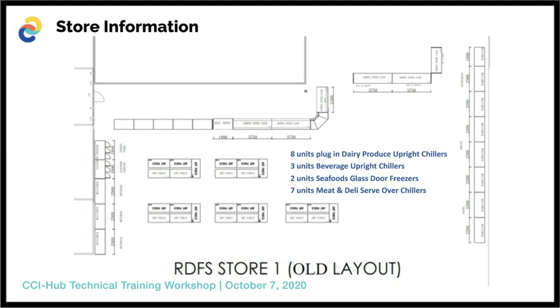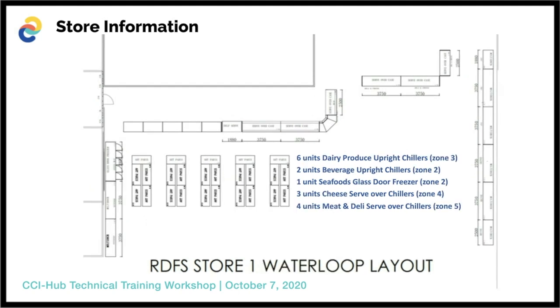After the renovation of the store itself, the way we did the renovation was all wall-mounted refrigerated units are part of the water loop system. The island freezers in the middle are actually plug-in, but are also R290 systems. If you add up the number of units we have here, we actually have 16 units as opposed to the 20 that was the original setup of the store. But because the units are actually larger, the storage facility of the refrigerator unit actually has not changed. It's still approximately 780 square meters.